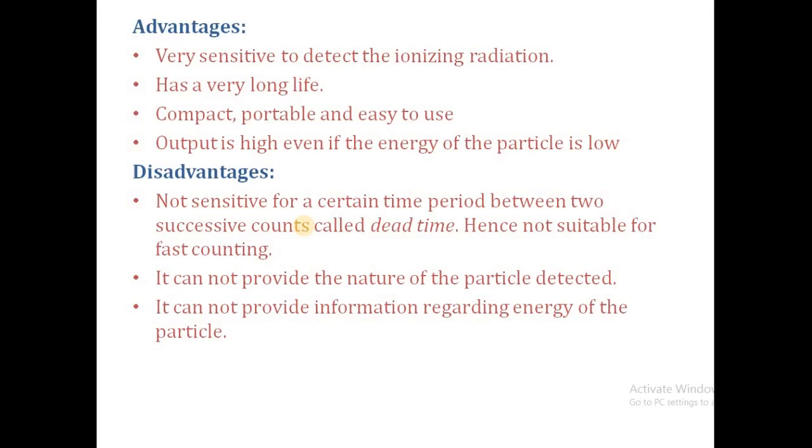Next, some of the disadvantages. The GM counter is not sensitive for a certain time interval between two successive counts. That time interval is called dead time, which is of the order of 200 microseconds. Hence, the detector is unsuitable for very fast counting. The GM counter can't provide the nature of the particle detected in the counter, and it also can't provide information regarding the energy of the particles detected.